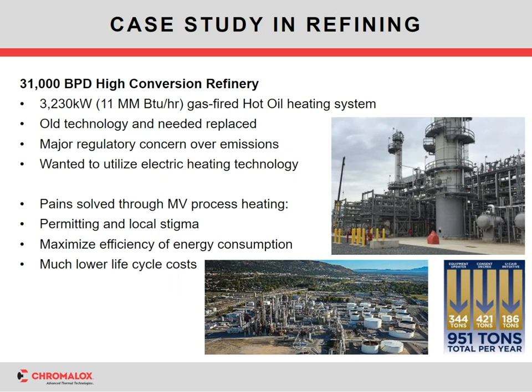So in our first case study, we want to look at a refinery that had an issue where they needed to replace a 3,000 kilowatt gas-fired hot oil system out there. Now the refinery had been built about 50 years prior, and when it was first installed, they didn't have to worry about pollution concerns or emissions. But going forward, they were up against their emission limits, and they weren't allowed to add any new fossil fuel-fired systems.